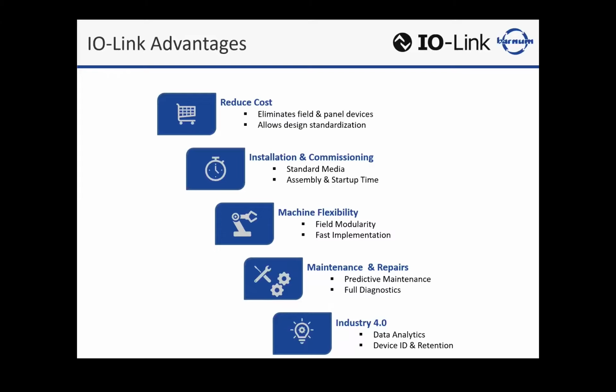And all those diagnostics, that's obviously going to lead into Industry 4.0, where people remotely can get information, data, information of what's the pulse of their equipment, what's actually happening on their equipment. So IO-Link has made that possible, and it's going to be the major stepping stone. Would you agree? Yeah, absolutely. More and more companies in manufacturing want to see the status at the device level to make sure whether it's predictive maintenance or reducing bottlenecks. Mm-hmm. They want to make sure they're optimizing the equipment.